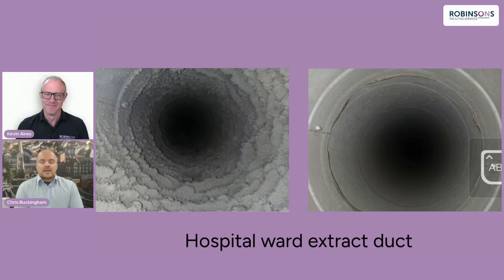No, exactly. And the main issue is when you're using the ventilation for something else. So in the industry that we're in as well, your fire safety works would involve things called fire dampers. I won't go into them too much because it's a little bit off from what we do, but fire dampers are located within the ventilation ductwork. And when you drop that damper down, it's very loud and it can be quite a shock. If you drop some of those anywhere near this buildup, there's every good chance of a problem.